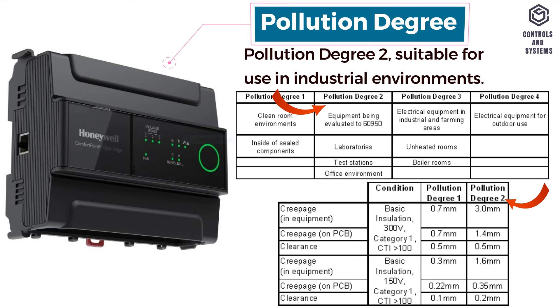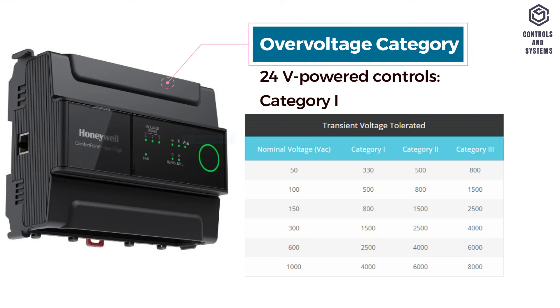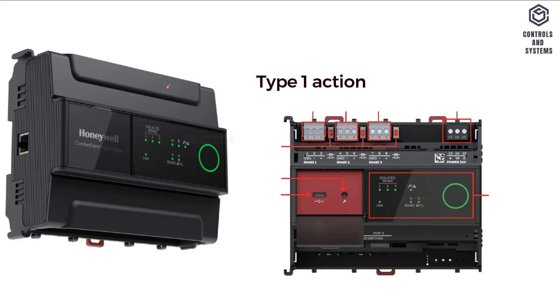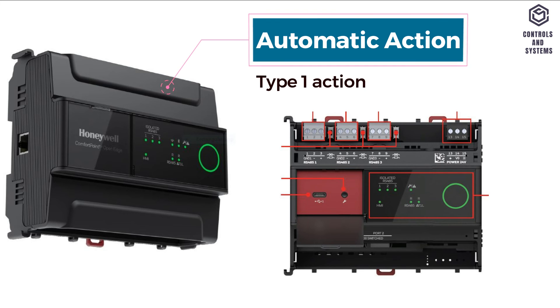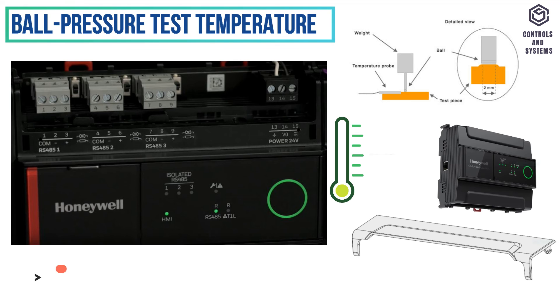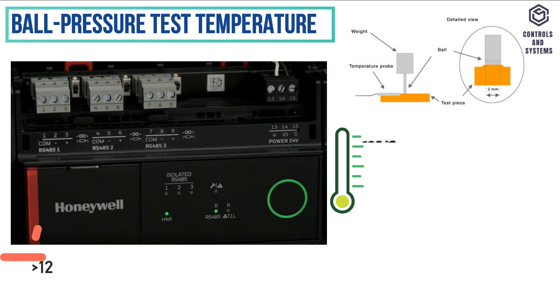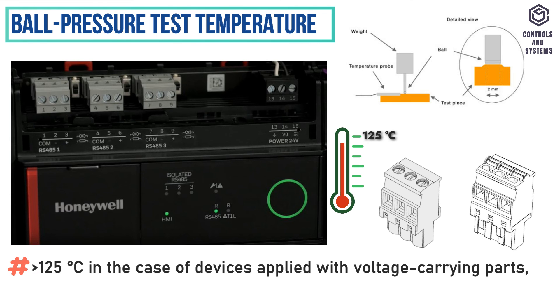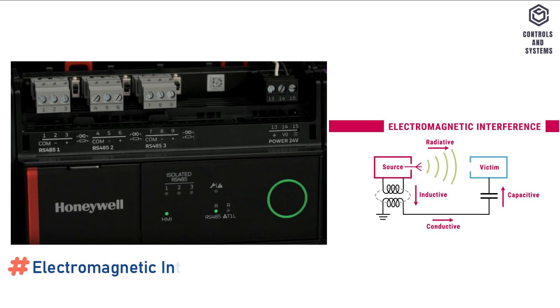Safety Information: Electric Shock Protection is SELV, Pollution Degree is 2, Overvoltage Category is Category 1, Rated Impulse Voltage is 330 Volt AC for Category 1, Automatic Action is Type 1 Action, Software Class is Class A. Ball Pressure Test Temperature: greater than 75°C for all housing and plastic parts, and greater than 125°C for devices applied with voltage-carrying parts, connectors, and terminals.